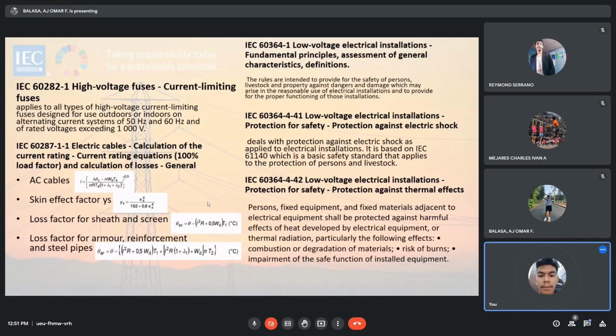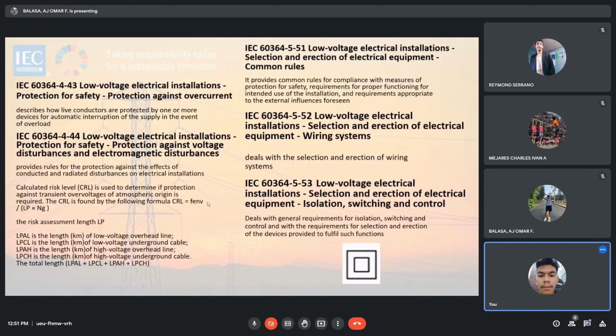Next, IEC 60364 Part 443. Low voltage electrical installations, protection for safety, protection against overcurrent. Protection can be achieved by limiting the overcurrent to a safe value or duration. It describes how live conductors are protected by one or more devices for automatic interruption of the supply in the event of overload.